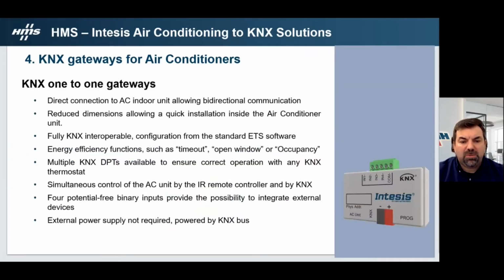On our KNX one-to-one gateways, we have direct connection to AC indoor units, allowing the bidirectional communication. The KNX one-to-one interface has reduced dimensions. This allows a quick installation inside the air conditioning units. We count with the fully KNX interoperation since our KNX one-to-one gateways are configured by the ETS. Our gateways have energy efficient functions such as timeout, open window, or occupancy. Multiple KNX data points are available to ensure correct operation with any KNX thermostat. It's possible to have control from the AC unit by the IR remote control and by the KNX.